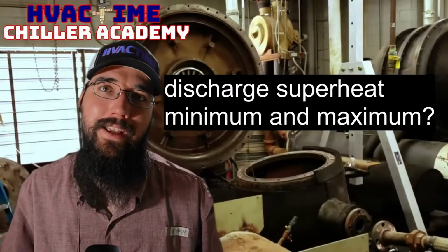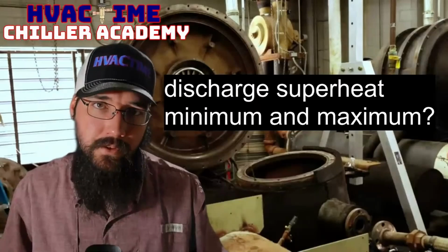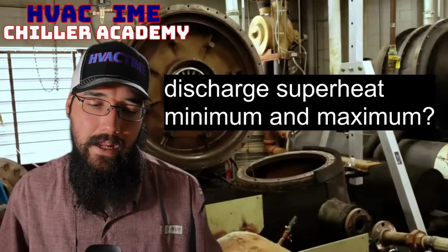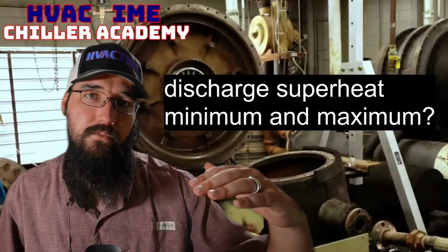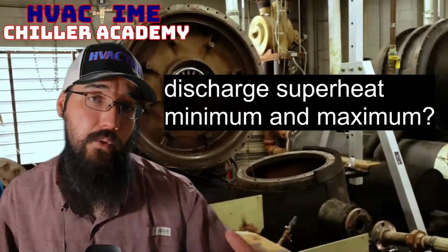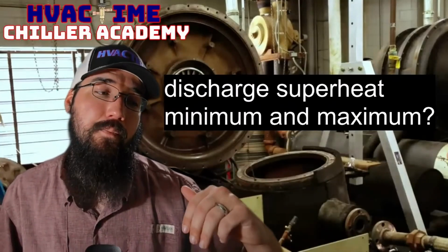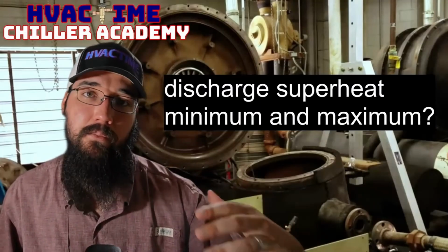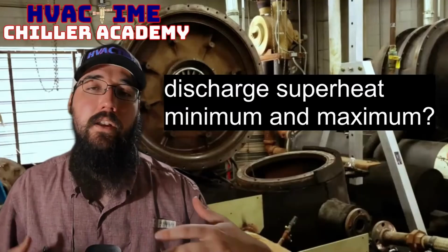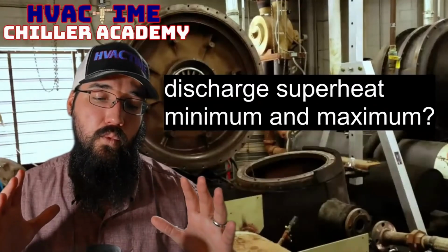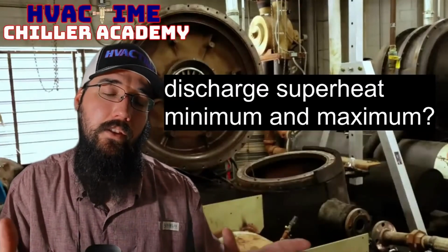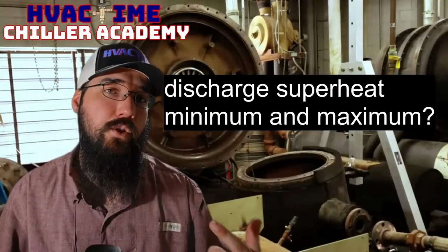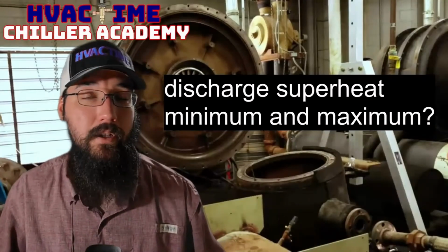Now if I'm below 10, something's wrong. Something is wrong as far as I'm concerned. And I'm going to start looking first and foremost at where that liquid level is in the evaporator, whether it be an overcharge or overfeeding, we could have a metering device issue. There's a few things, but when you start getting below that, and the closer you get to 5 and less especially, that's when you start getting into liquid droplet territory.